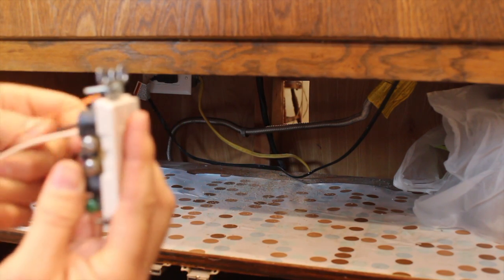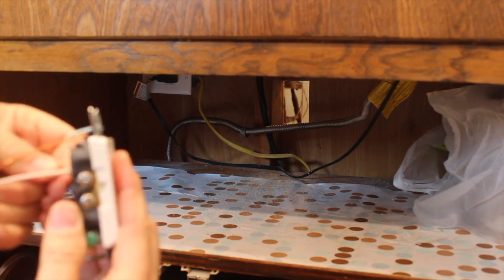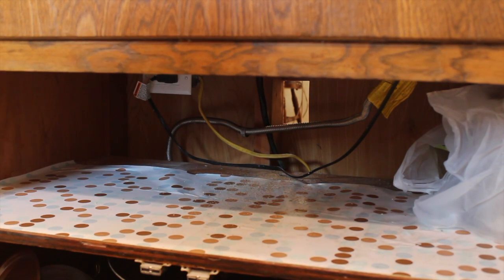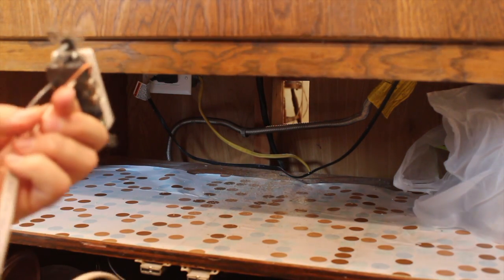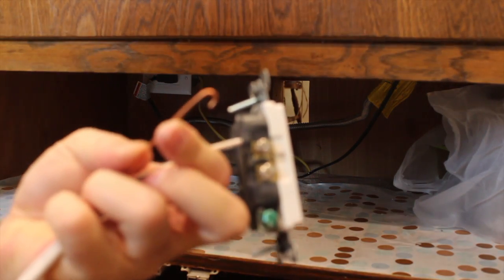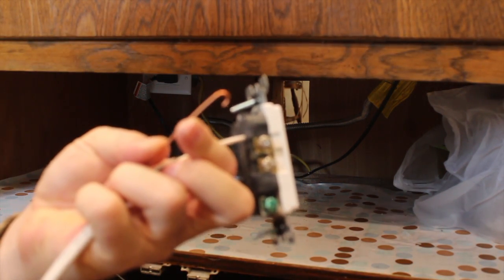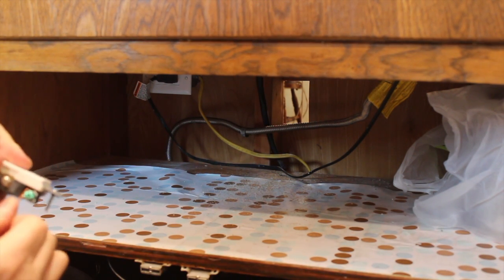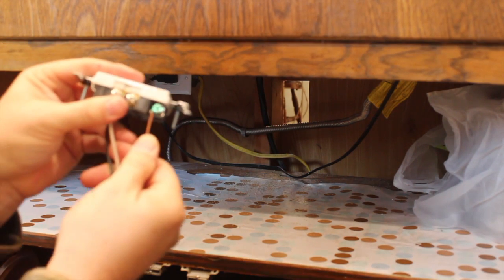I can insert through like that. I wanted to kind of pre-wire this whole thing. So black on black, they mark it right on there. This side is the white side, that's the black side, and the ground goes down here on the green. So there's a white wire and these ones have an insertion hole you just push right in, real simple. Just like that. Then you take the end and put a little curl right there and hook that on the green screw.